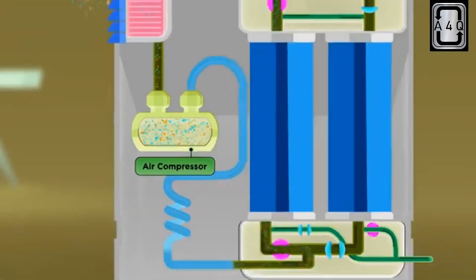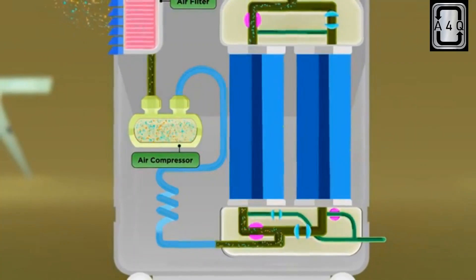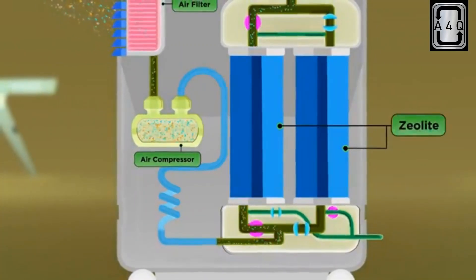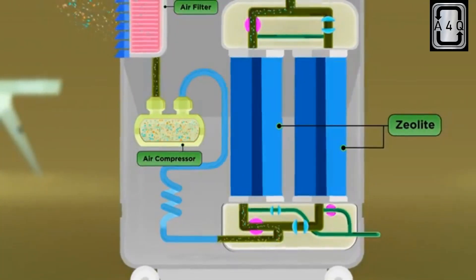This purified air has been compressed. The compressed air passes over a filter made of zeolite. This is a molecular sieve bed made of special material that is selective towards absorbing nitrogen more than it is towards oxygen.